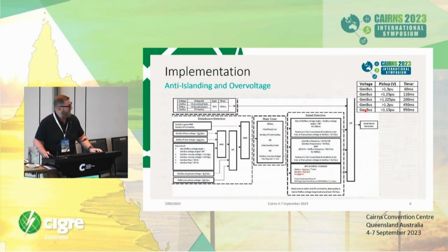To give an idea of what kind of logic we're implementing, basically there are overvoltage elements at the generator bus. There's some undervoltage protection that takes into account the strength of the reference node compared to the generator bus. And then the main part of it is disturbance detection. So a fault has happened. We wait a period of time for the fault to possibly clear. If the conditions are continuing, such as a phase angle difference or frequency difference between the 2 systems, we'll then operate as needed.